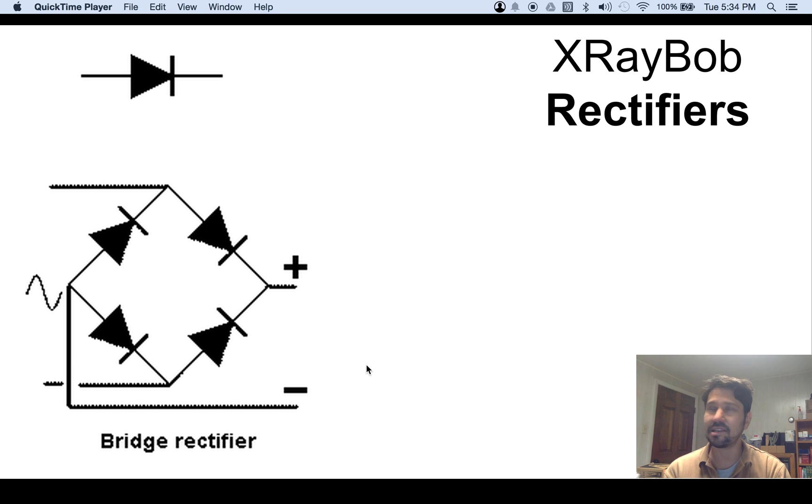So the last thing just ahead of the x-ray tube is the rectifier circuit, which converts AC to a high voltage DC. Well, converts high voltage AC to DC.